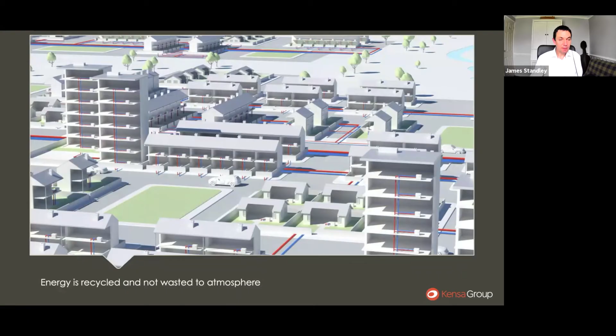All of the waste heat produced by the cooling goes into the ambient temperature loop, and all of the cold produced as a byproduct of the heating goes back into the loop. So we're not wasting that energy out to atmosphere. One benefit is that the efficiencies of both the heating and cooling systems are improved, and you can also store that energy in the loop between the heating and cooling applications.